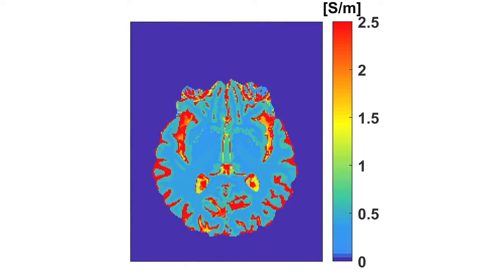for the scientist. The conductivity imaging is made easier by having a very good balanced fast field echo sequence, for example, which is the main one that we're using. You can also do this with the turbo spin echo. The turbo spin echo has probably less phase artifact in it, but we've managed with the bFFE to reduce the artifact to the point where it's almost minimal. And again, that is because the system generates very, very nice phase maps for us.